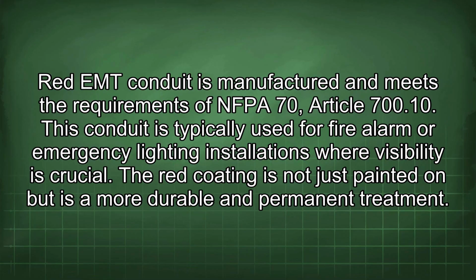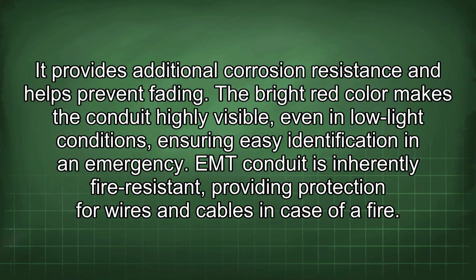Red EMT Conduit is manufactured and meets the requirements of NFPA 70, Article 700.10. This conduit is typically used for fire, alarm, or emergency lighting installations where visibility is crucial. The red coating is not just painted on, but is a more durable and permanent treatment. It provides additional corrosion resistance and helps prevent fading.